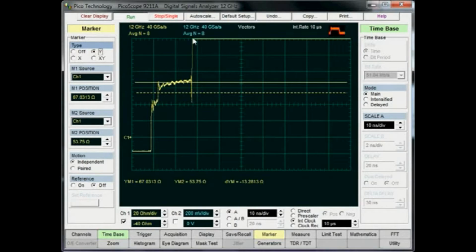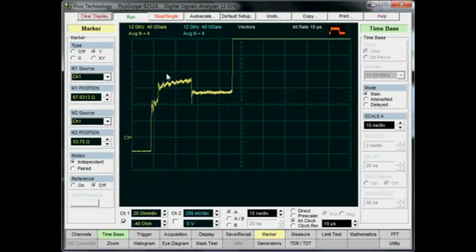This is the output going to a very high impedance, so I'm going to connect, as a second example, a length of 50 ohm cable to the T-piece at this point. So I'll connect my 50 ohm cable, just clear the display, and here we can see now the 75 ohm cable and then some 50 ohm cable. I could put my second marker on that point and see here that it's indicating this cable has a mean impedance of 55 ohms.